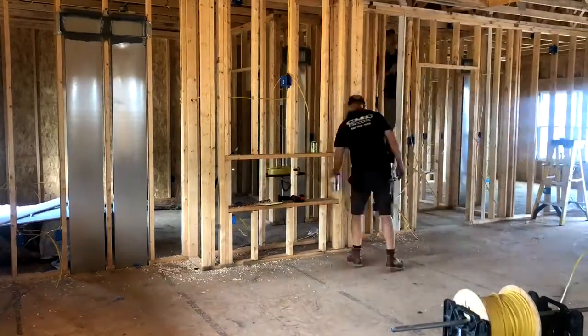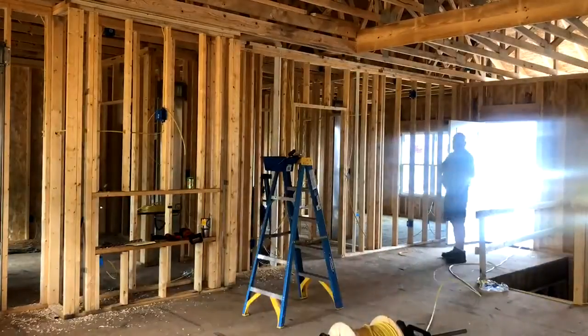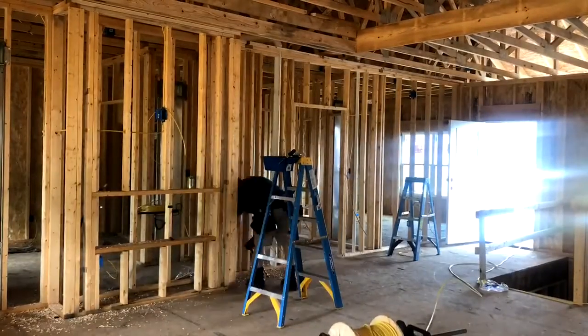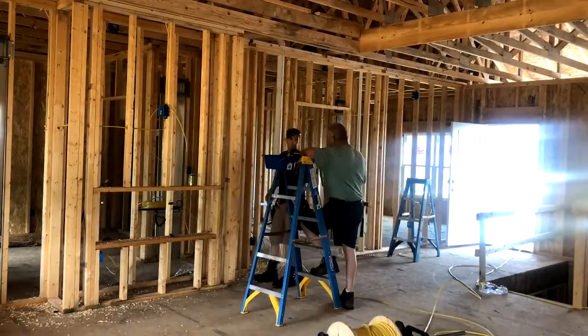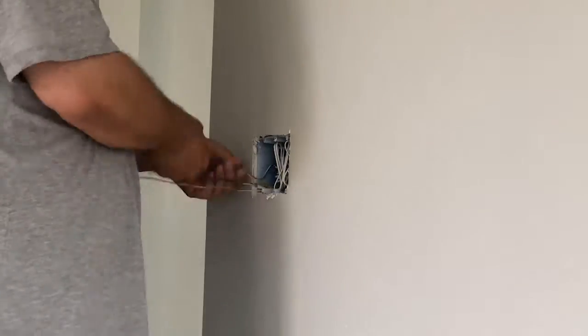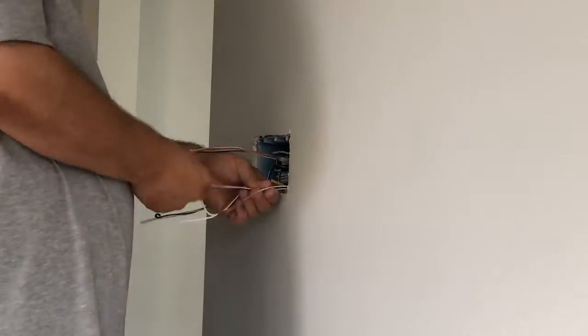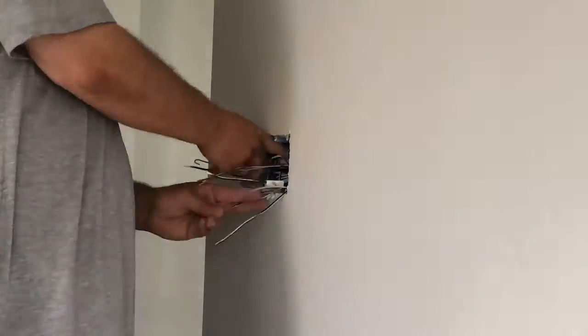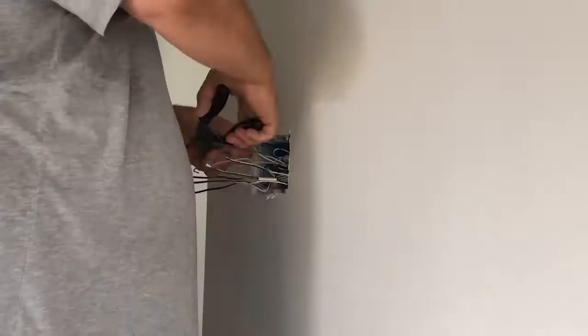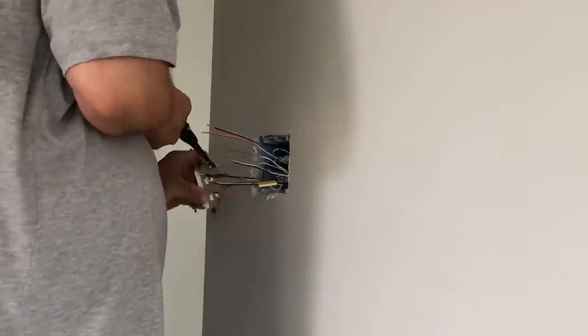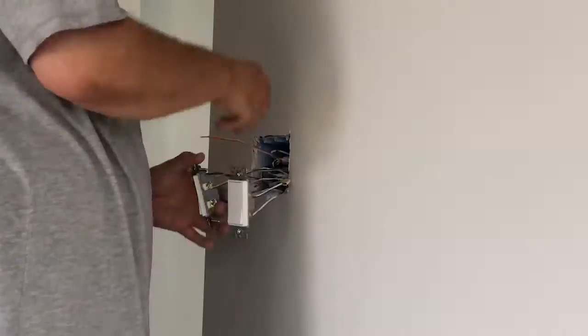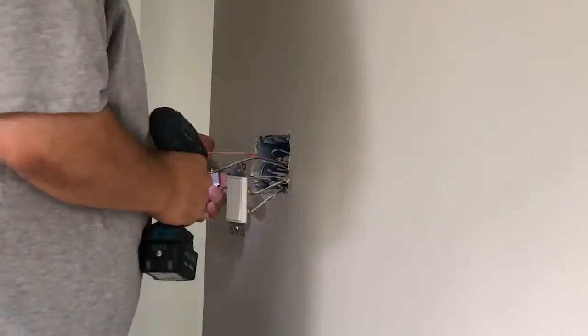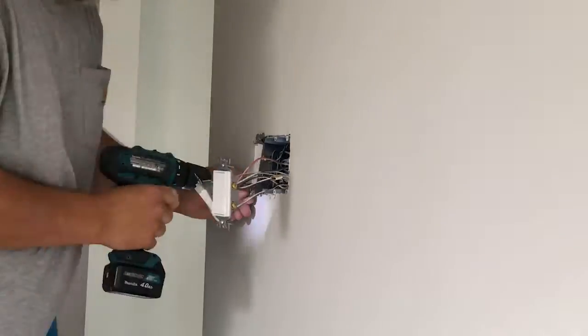Then once the project has been drywalled and painted, we come back and do the trim-out. This is where we install the actual light fixtures, ceiling fans, recessed light trims, as well as all of the switches and receptacles. We will also wire the furnace and air conditioner and install all of the hardwired smoke detectors.